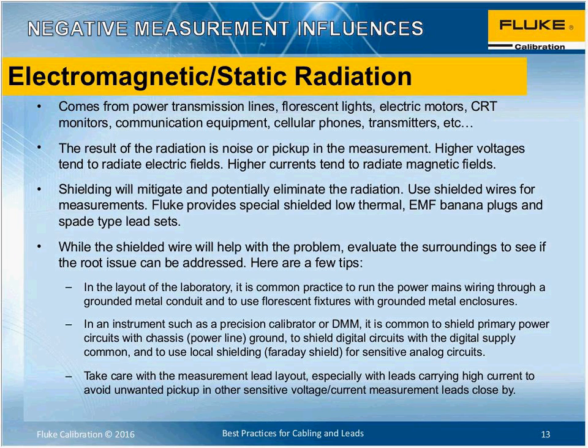These days, it's a little bit less of a problem with our LCD monitors, but the CRT, cathode ray tube monitors that we might have had with the computers, which rely on magnetic fields for deflection and big old power supplies, could cause a problem. We have, of course, nowadays, the communications equipment. We have to be a little bit careful about the siting of our wireless LAN access points, and of course, cell phones in our pockets are some other problems. In many laboratories, the use of cellular telephones and similar transmitters is discouraged or banned completely because they can produce some quite high signal levels very, very close to the instrumentation. And even if you're doing low frequency DC work, if there's something there that could cause some of that RF energy to be rectified, it can still cause problems with DC measurement.